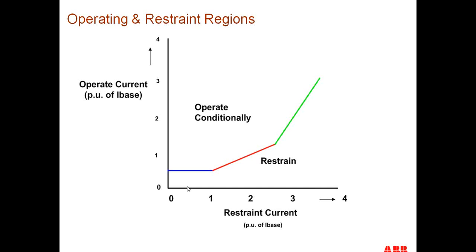Because now we have a relationship between the restraint current and the operating current, we also have an operating curve for the relay. So we actually have three different slopes for the modern microprocessor relays. One is a straight line, 0% slope, that's good up to a certain point, like 1 per unit restraint current. The next has a slope of about 40%, which you see in the red area, and this is good between 1 times and 3 times the normal restraint current. And then above 3 per unit restraint current, we have a line that goes up at an 80% slope.